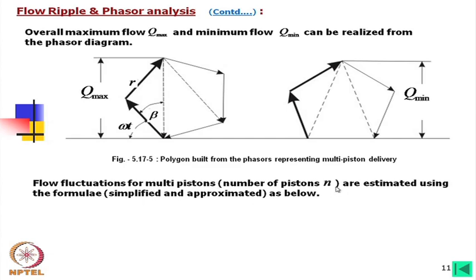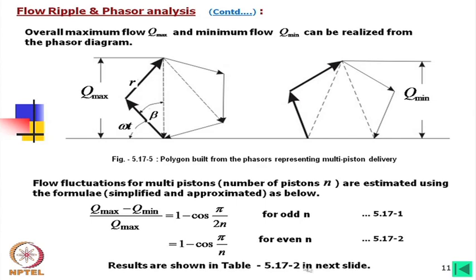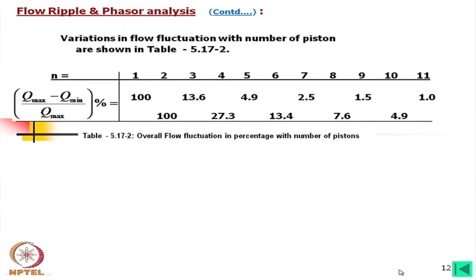Flow fluctuation for n pistons is estimated using simplified approximate formulas: for odd n, the fluctuation ratio is 1 − cos(π/2n), and for even n, it is 1 − cos(π/n), where n is the number of pistons. These values are presented in a table for multiple different cylinder counts.